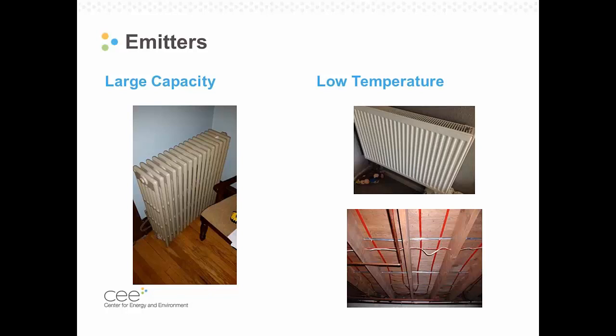Additionally, any new systems that have been installed tend to be these lower temperature systems. At the top on the right, you can see a radiant panel that's designed for about 140 degree supply water temperature. At the bottom, you can see a radiant in-floor system, and that's designed to be maybe a 95 to 105 degree supply water temperature. And so these newer low temperature systems are designed to work better in condensing systems. So both of those outcomes really helped to ensure that 90% efficiency.